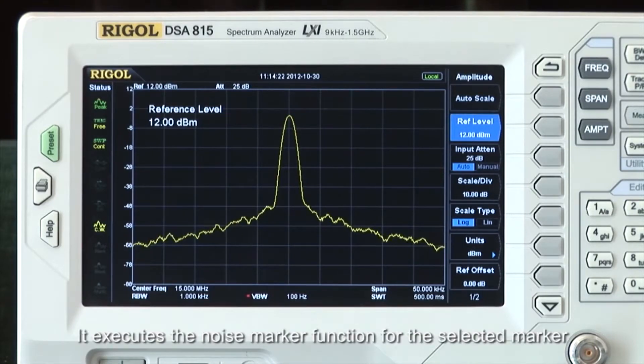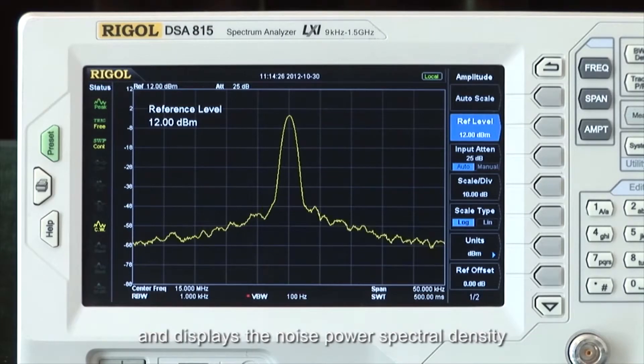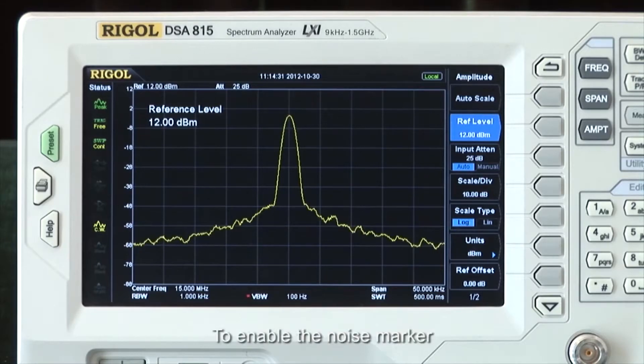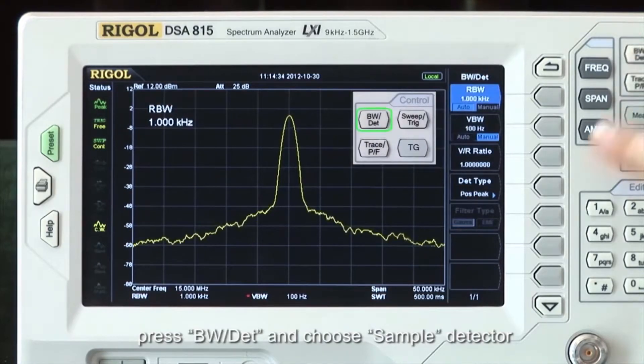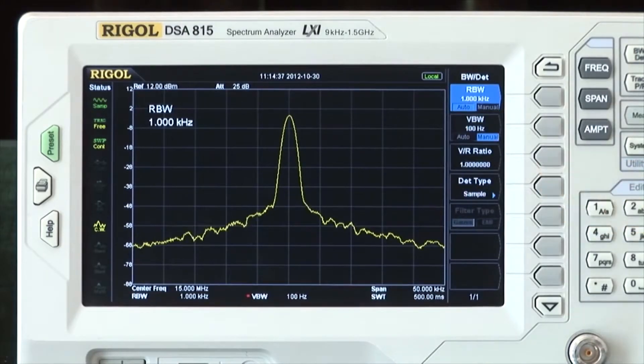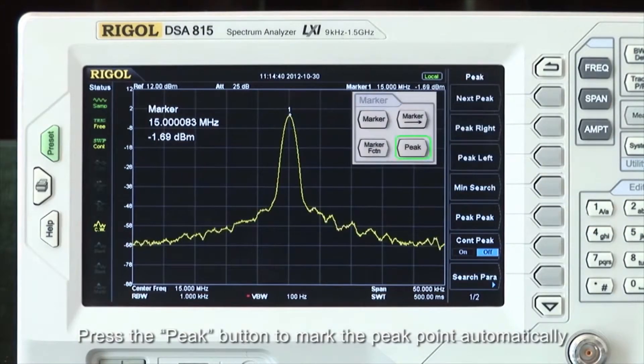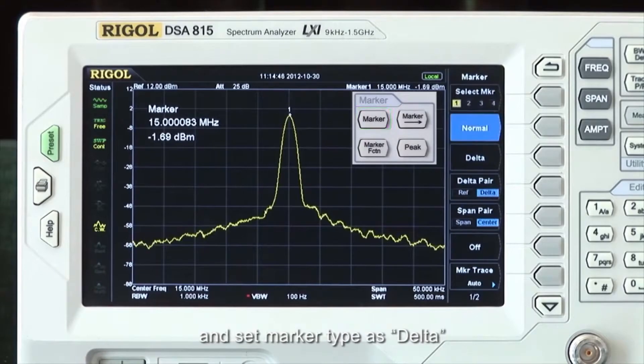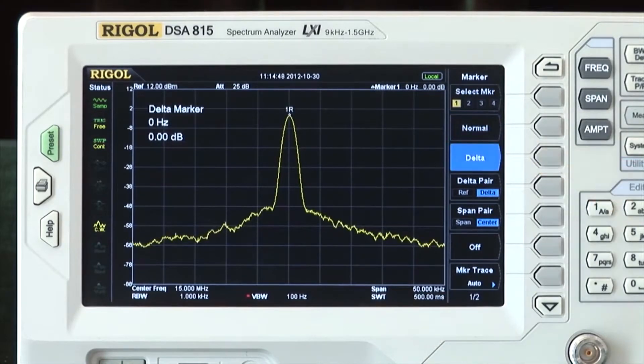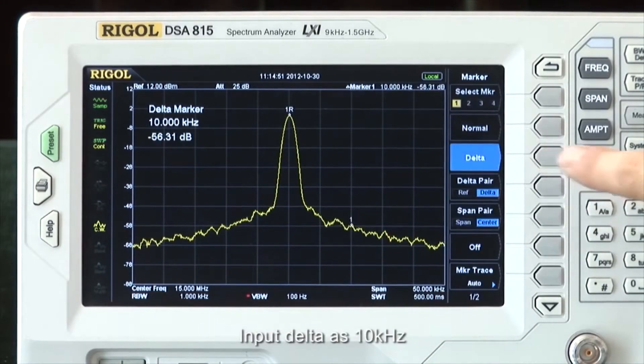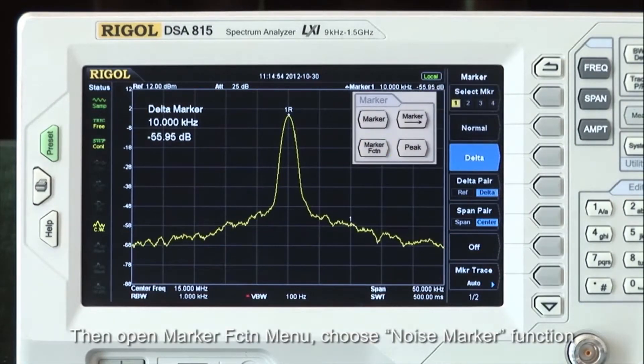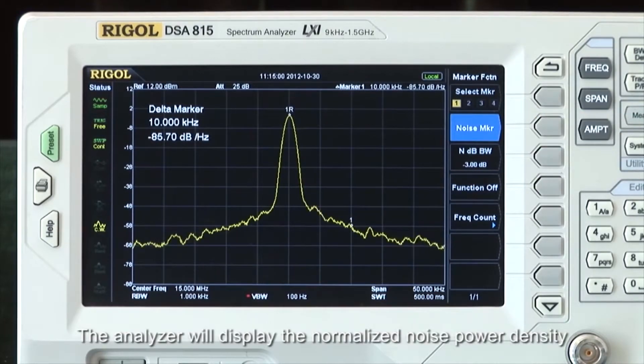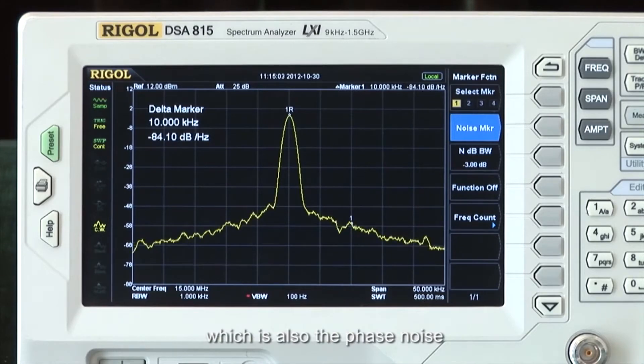The noise marker function executes for the selected marker and displays the noise power spectral density. To enable the noise marker, press bandwidth detector and choose sample detector. Press the peak button to mark the peak point automatically. Then press the marker button and set the marker type as delta. Input delta as 10 kHz. Then open the marker function menu and choose the noise marker function. The analyzer will display the normalized power spectral density, which is also the phase noise.